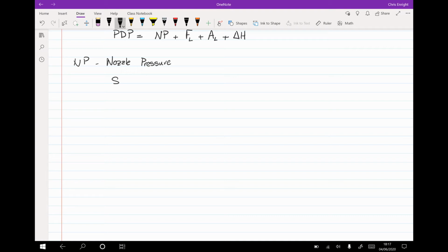So when we look at this handful of nozzles that we're realistically considering, first, smooth bore. We have a couple of smooth bore nozzles on our trucks. These obviously require the lowest amount of pressure. They need about 50 psi at the tip, or at the entrance to the nozzle. The reason for this is pretty simple: a smooth bore nozzle just tapers down. It's a single piece of metal, so water flowing through doesn't encounter a lot of resistance, it just gets necked down, and that gives us a good pattern out the end.